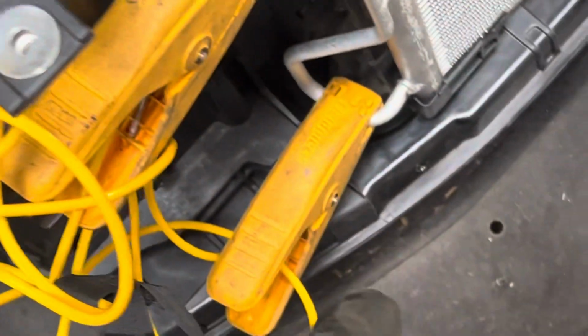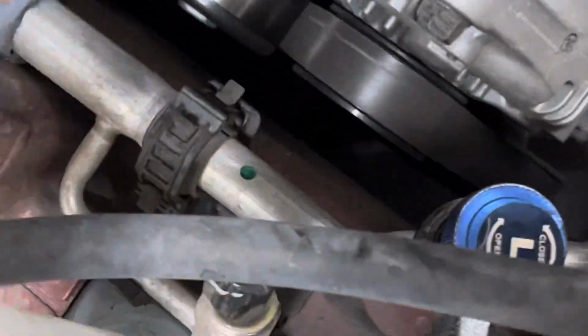Let's look at some temperature changes. Let me grab this guy right here. And we're going to go after the heat exchanger. So let me grab a piece right there. There we go. So that's the suction line before or after, however you want to word this. But if you look right here, here's the liquid line going in. This is the internal heat exchanger that has liquid traveling on the outside of the suction line returning to the compressor.